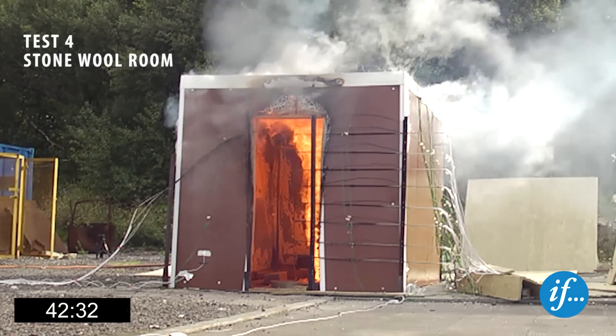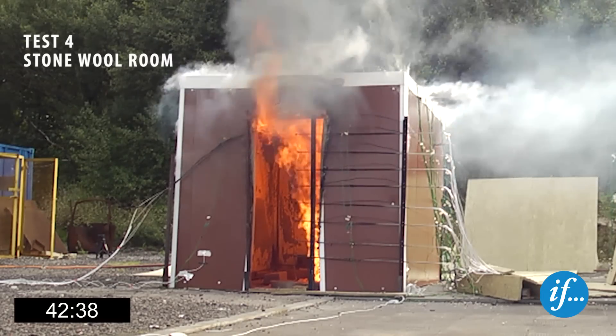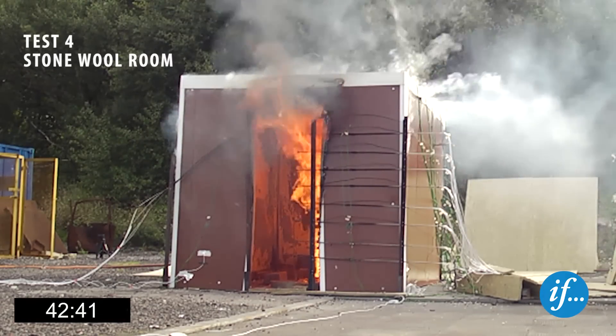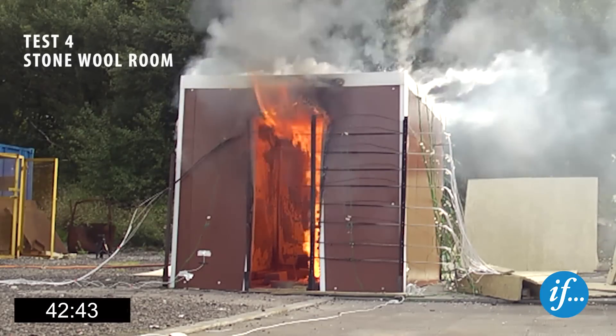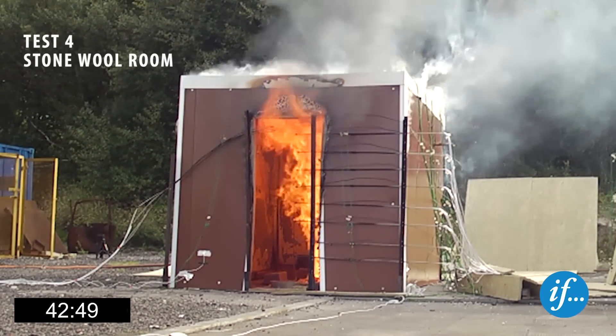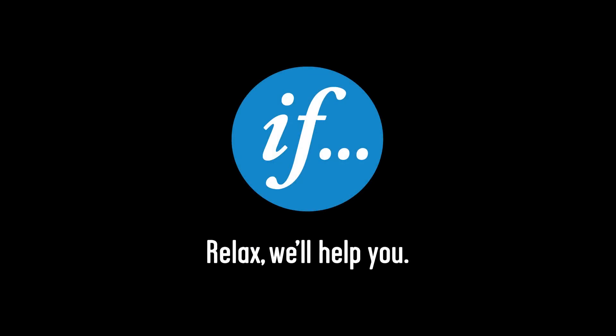After forty-two minutes, the temperature in the stone wool room has increased to approximately 800 degrees Celsius. The test is allowed to continue, reaching a peak temperature of 900 degrees Celsius after fifty minutes. The test is extinguished after sixty-four minutes. For more information, please refer to the article in If's Risk Consulting Magazine, which can be found by following the link on the screen.